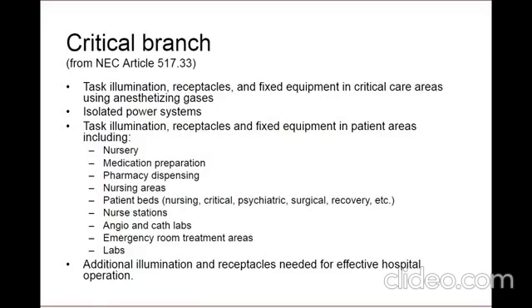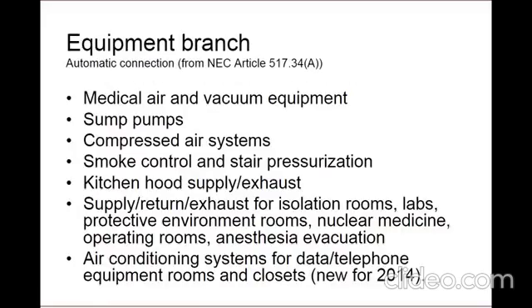But then, of course, and if that was not enough, it then gives you that coverall of additional illumination and receptacles needed for effective hospital operation. So as I mentioned, this allows you to include other things that aren't necessarily listed here as new departments continue to emerge in hospitals or whatever. This doesn't preclude you from putting imaging departments on emergency power because you have that caveat there.